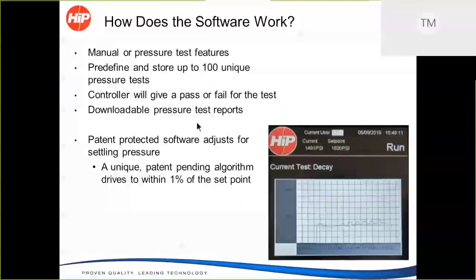So one thing that's important to note on this system, we actually have a unique pressure testing profile. That's actually a patent-protected technology that we have, where anyone who's run a pressure decay test will be able to understand that it's very difficult to hit a target pressure exactly. So for example, if you're running a pneumatic test and you want to run at 10,000 psi, you might drive that pneumatic pump up to 10,000 psi, and as soon as you turn the air pressure off to that pump, the system's going to relax, which would mean you'd ultimately see the fluid pressure drop a little bit. So let's say hypothetically in this case it drops to 9,000 psi, and then you're going to try to do your pressure decay test there.